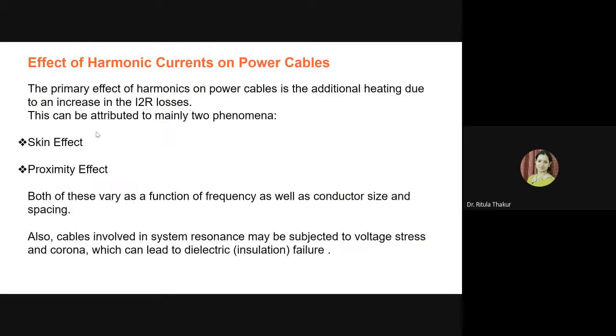Now, apart from the transformers, the effect of harmonic current on power cables is also prominent. The main effect of harmonics on power cables is additional heating due to the increase in the I-square R losses. We have just discussed this, and in the case of cables it is attributed mainly to two phenomena, skin effect and proximity effect. I will not go into much detail on skin effect and proximity effect because many of you are from multidisciplinary backgrounds, but I just want to give you an idea of how our appliances and distribution assets are getting disturbed.